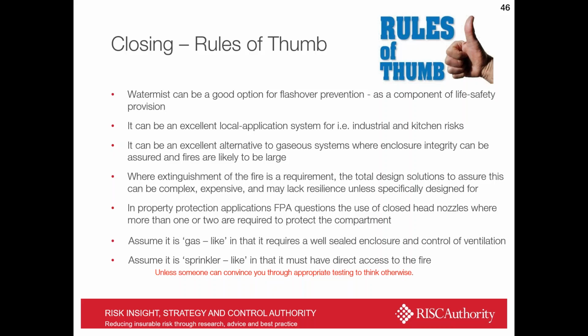In property protection applications, FPA questions the use of closed head nozzles where more than one or two are required to protect the compartment. So in small compartments, where you may only have one or two bulbed heads, such as a domestic and residential or hotel type environment, it's probably fine. But to protect large open floor areas with bulb systems, we still think there is more work to be done before that would be advised.